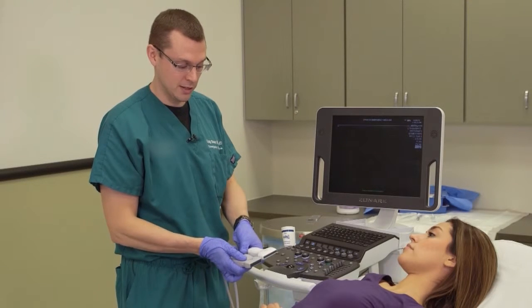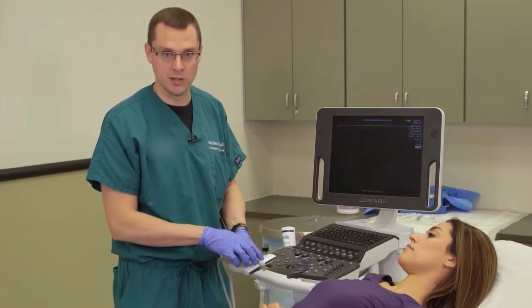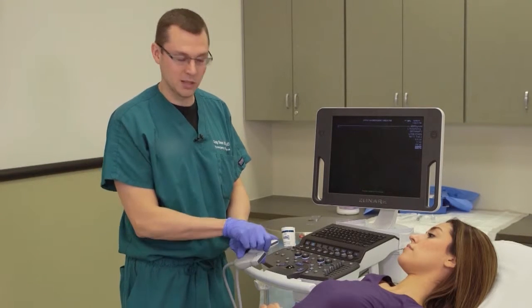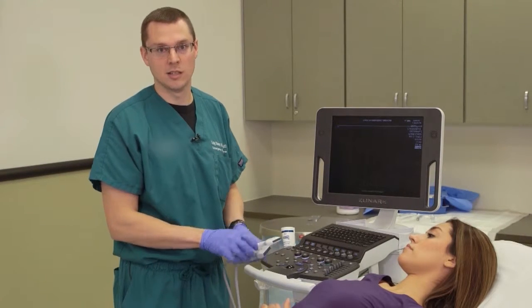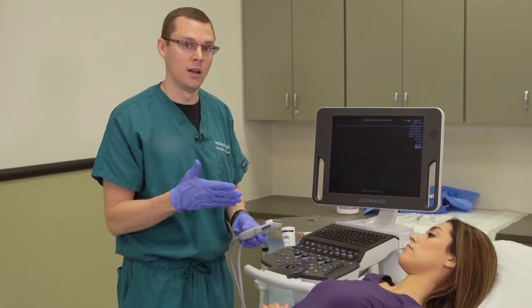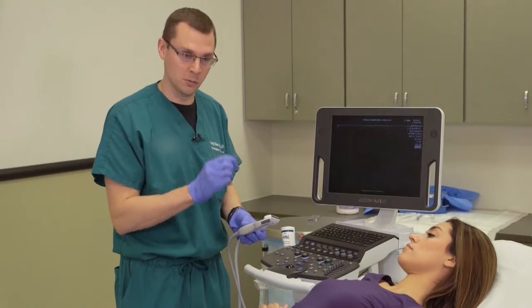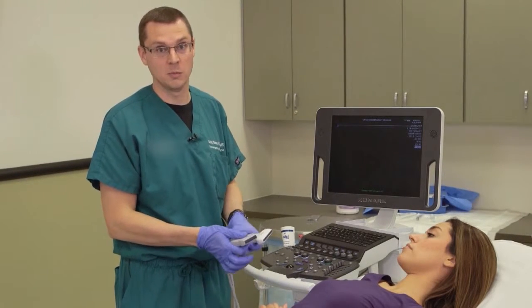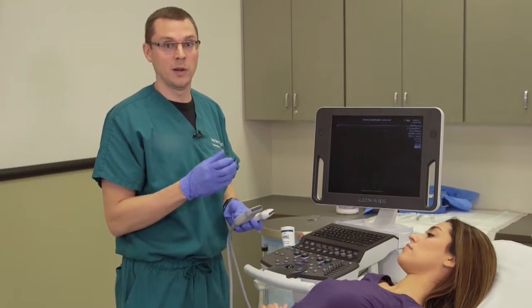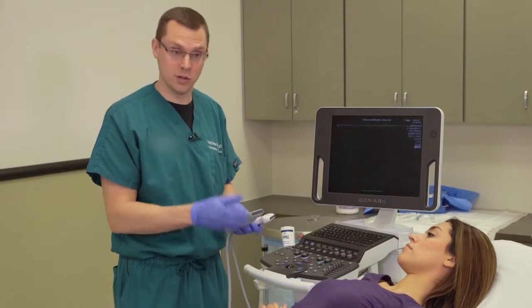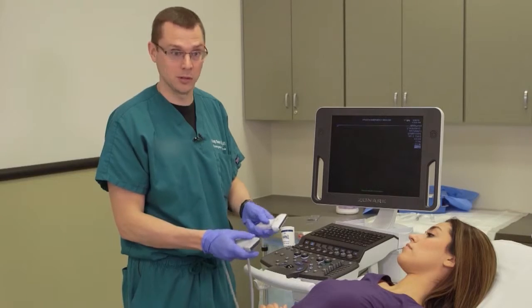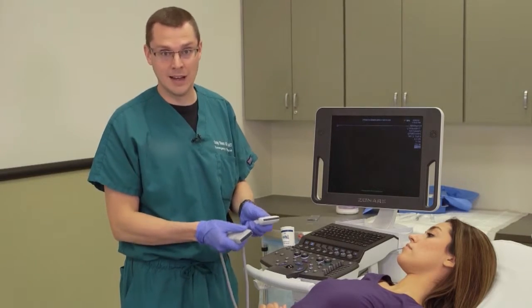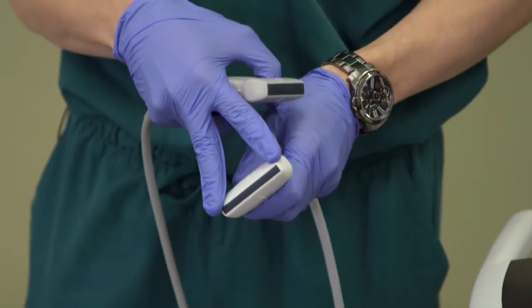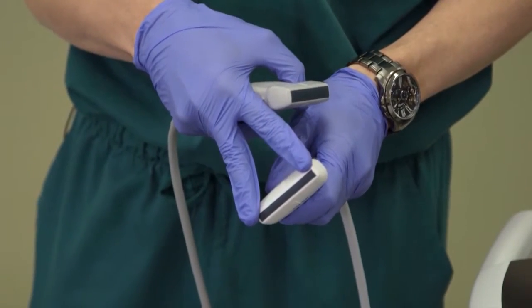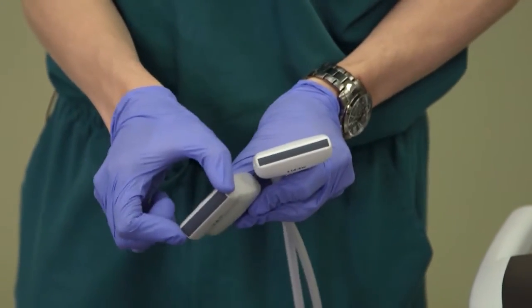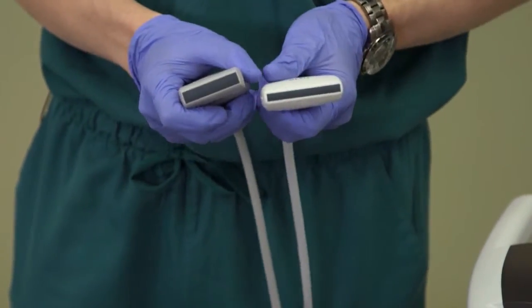The different transducers are going to have different frequency ranges. Since the footprint is a little different, the frequency range is going to determine your axial resolution for the ultrasound machine, or picking out different points. A higher frequency is going to give you better, clearer images of small structures than a lower frequency. However, with some patients who have sunken-in eyes, you may not be able to get the entire footprint into a place where you can get a very good image, and you might want one that's a little bit smaller. So it's going to be based on the patient that you have.